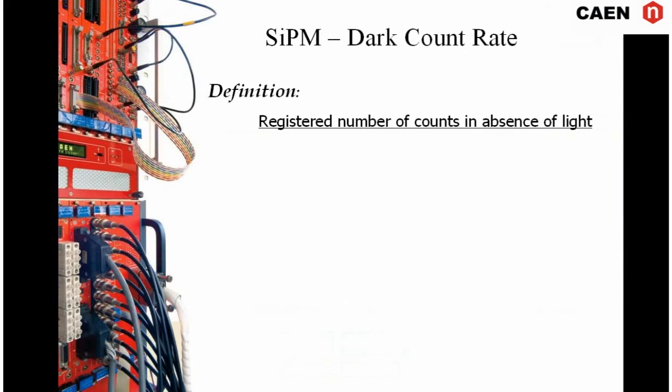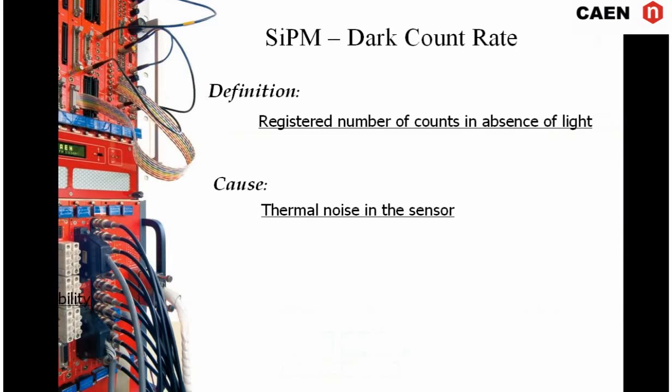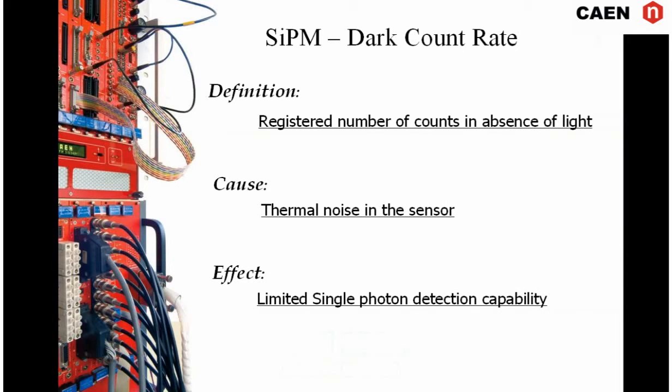The dark count rate is represented by the registered number of counts in absence of light. These counts are generated by thermal noise in the sensor and limit its single photon detection capability. It is measured like a frequency and it is essential in determining the silicon photomultiplier characteristics.